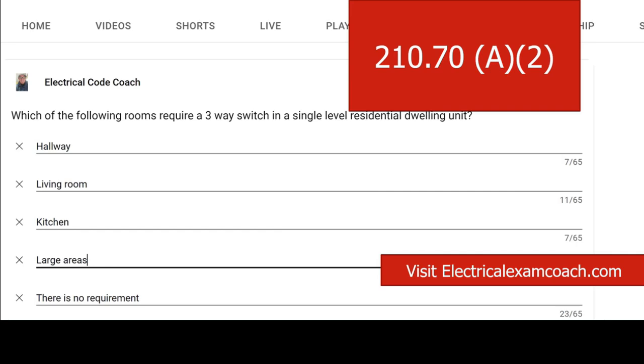And that is required for all stairwells on the interior of the home for a residential dwelling. And anywhere else in the code, it's just not required. Whether it's a hallway, living room, kitchen, doesn't matter how large the hallway is. You could have a 45-foot hallway and you would only be required to have one switch, according to the NEC.